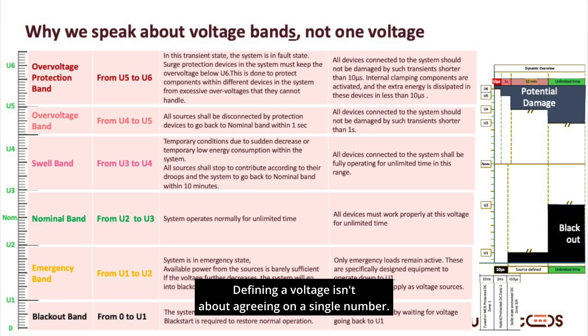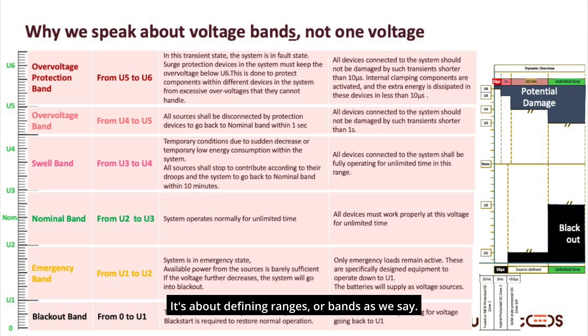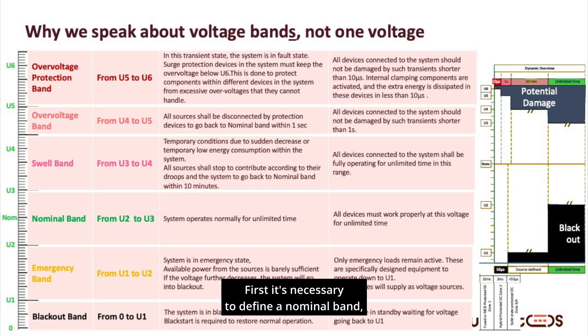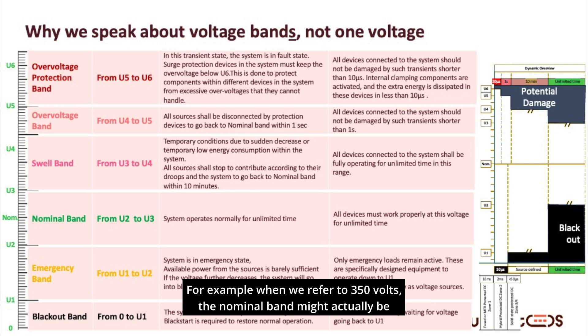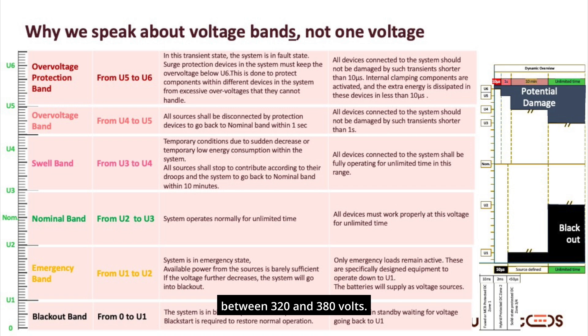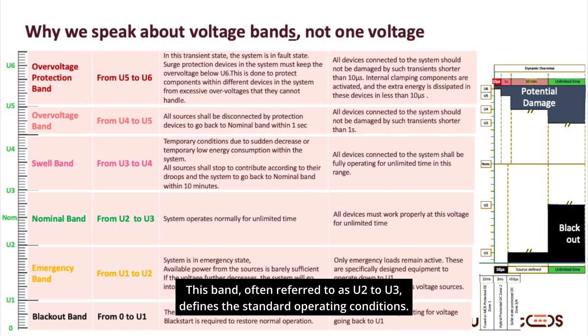Defining a voltage isn't about agreeing on a single number — it's about defining ranges, or bands. First, it's necessary to define a nominal band: the band within which the system operates indefinitely. For example, when we refer to 350 volts, the nominal band might actually be between 320 and 380 volts. This band, often referred to as U2 to U3, defines the standard operating conditions.